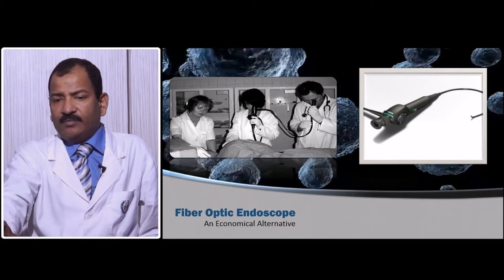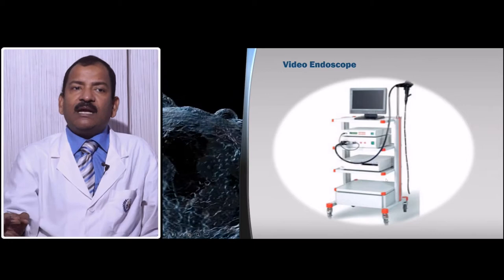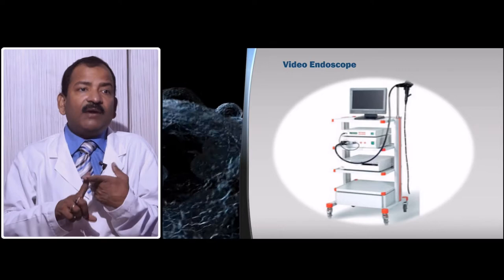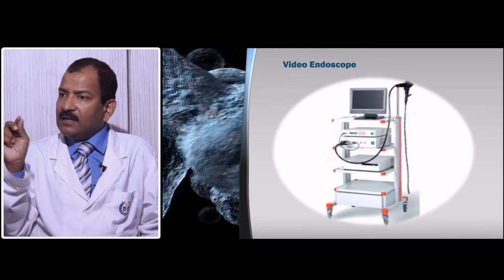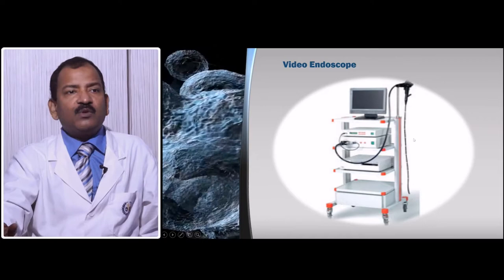Most people nowadays use the video endoscope. The video endoscope is completely digitalized — it has chip-on-tip technology, so the light fibers are only used to throw light inside, but the image is taken by the CCD (charge-coupled device) at the tip. The same charge-coupled device found in a laparoscope camera head is here at the tip of the endoscope, digitally capturing the image. There is a processor that can perform digital enhancement.